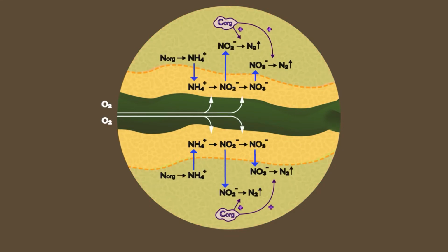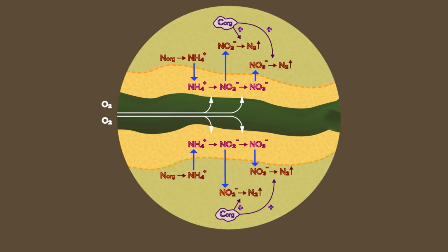Exactly. The essential point to remember is that every plant root develops an aerobic microzone around itself, around which, in turn, an anaerobic zone develops. The development of these two zones results in two basic processes: nitrification and denitrification. These two processes effectively remove nitrogen compounds from wastewaters. Makes sense? Yes. Excellent, Betsy.